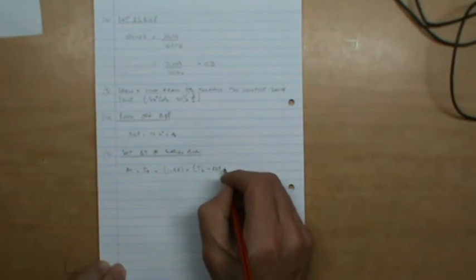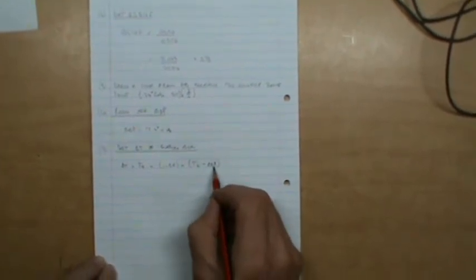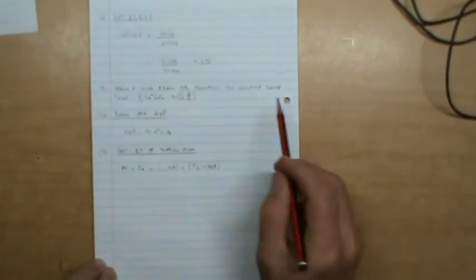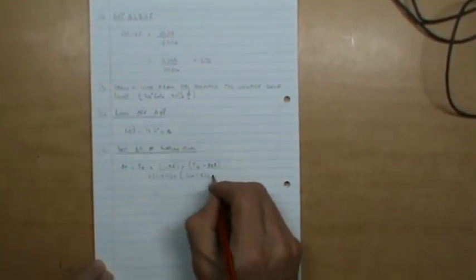Now please, ladies and gentlemen, the apparatus dew point, if you get it wrong, then the whole lot is going to be wrong from now on, and you'll get a couple of marks for what you've done, but the nuts and bolts of it is going to be wrong thereafter. Okay, so be careful, make sure that the apparatus dew point's right. 1 minus 0,2, which was our bypass factor, multiplied by temperature 2, which was 24, minus our apparatus dew point of 8,6 degrees Celsius.